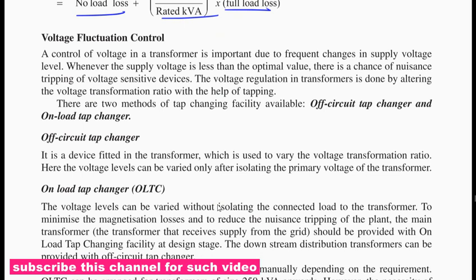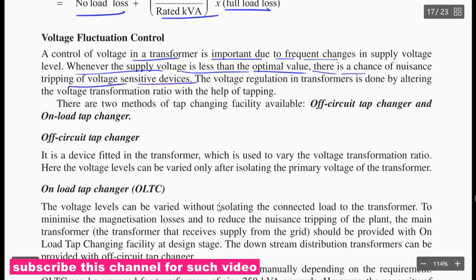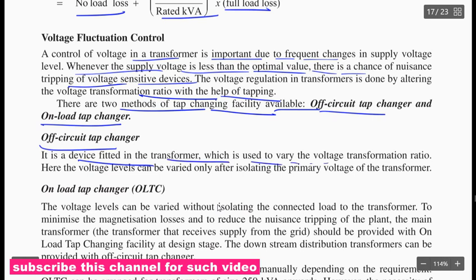Voltage fluctuation control. Control of voltage in the transformer is important due to frequent changes in the supply voltage. Whenever the supply voltage is less than the optimal value, there is a chance of nuisance tripping of voltage sensitive devices. Voltage regulation in the transformer is done by altering the voltage transformation ratio with the help of tapping. There are two methods of tap changing facility: off circuit tap changer and on load tap changer. It is a device fitted in the transformer which is used to vary the voltage, and it can be varied only after isolating the primary voltage and the transformer.